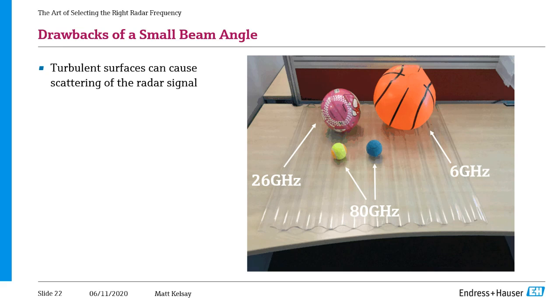So really choosing a frequency and a beam angle is really a balance, right? Because you don't always want that biggest footprint, because maybe you have a lot of obstacles in your tank, and it might be difficult to program the unit to ignore some of those. So a lot of times in turbulent applications, a 26 gigahertz radar is the perfect in between. And again, this is not a hard and fast rule, that you can't ever use an 80 gigahertz radar in an application where there's a little bit of surface turbulence. It's just another factor that plays into the selection.